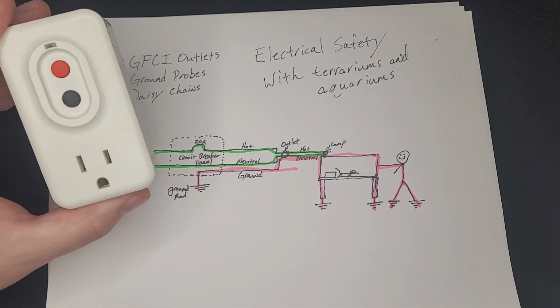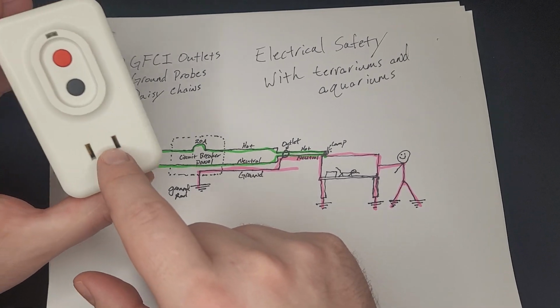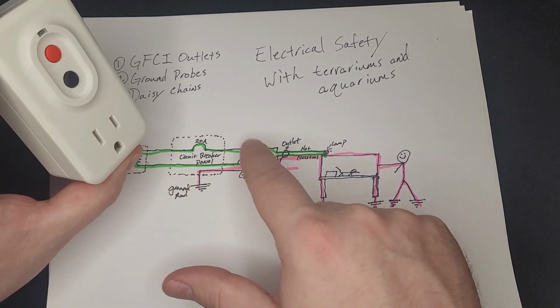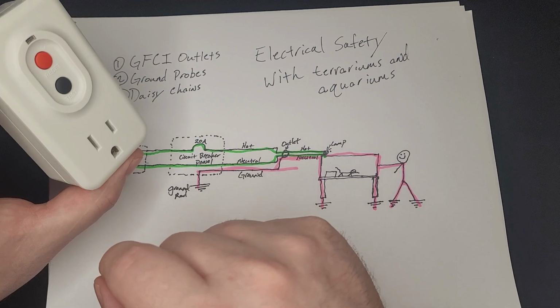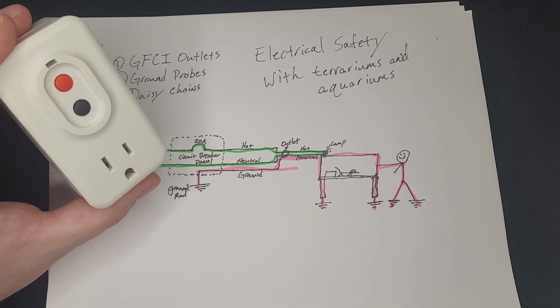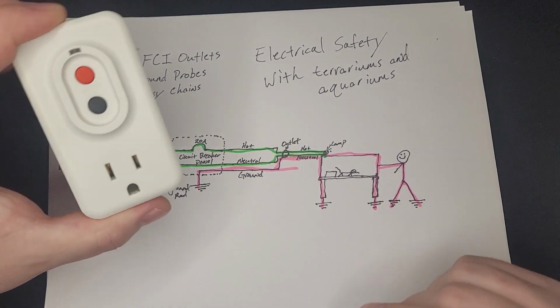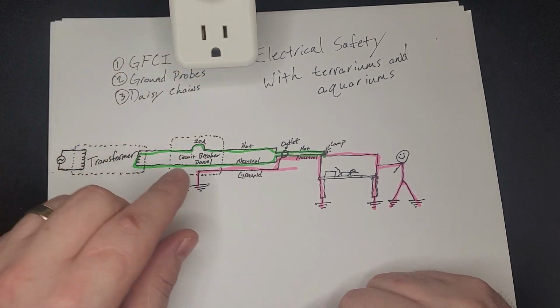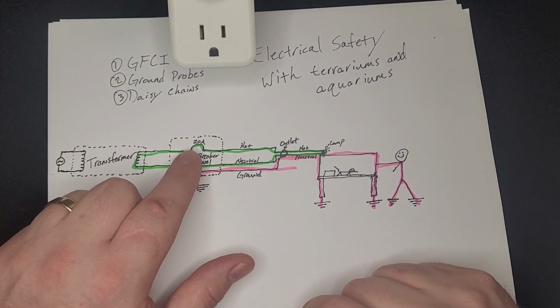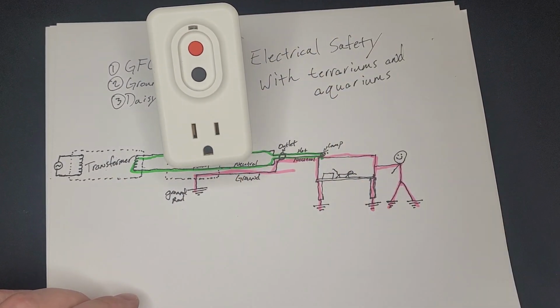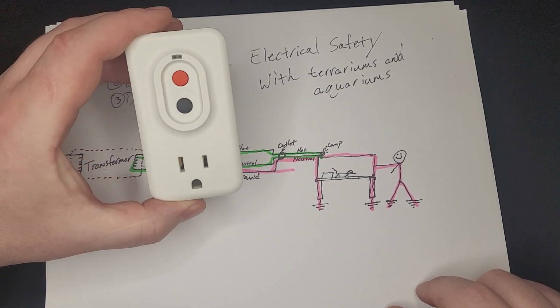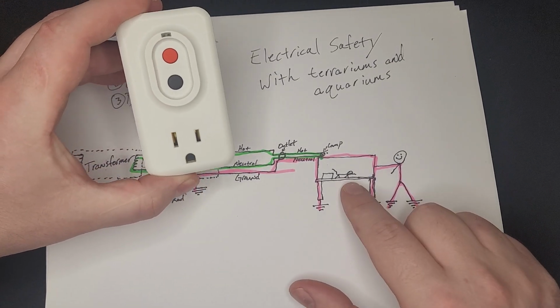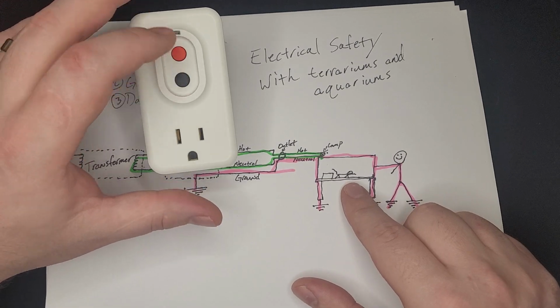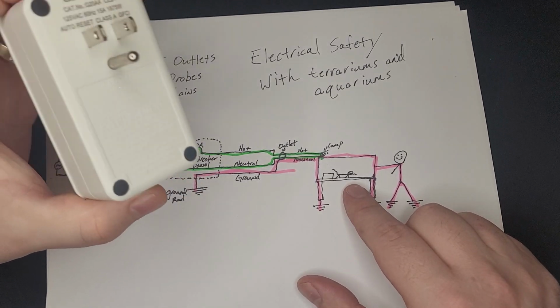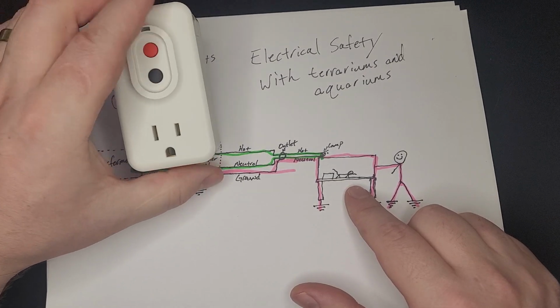These are called ground fault circuit interrupter outlets. What they do is monitor the electricity going through the hot line and watch for it coming back through the neutral line. If it doesn't see that electricity coming back, it shuts off the power, and it does this at a much smaller range. Whereas a circuit breaker trips at about 20 amps, this trips at about 5 milliamps, about 4,000 times less current going through your body or your terrarium. So it's much, much safer and much less likely to cause injury if you have one installed.